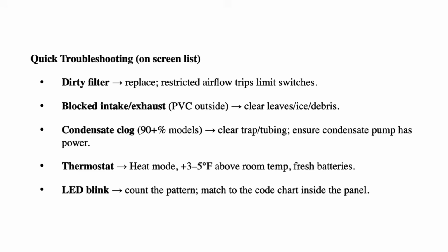LED blink: count the pattern and match it to the code chart inside the panel. When to call a pro: rollout trips again, burning smell, water pooling, igniter never glows, or repeated lockouts after fixes.